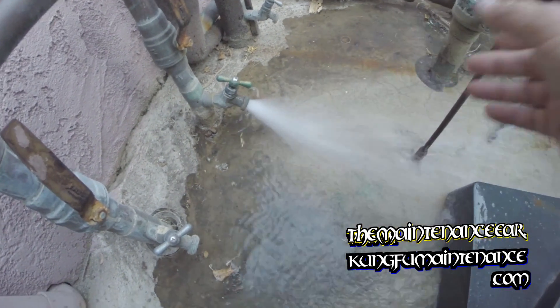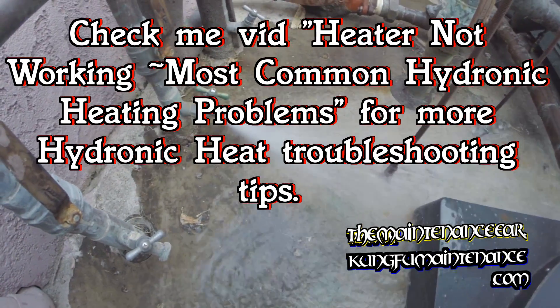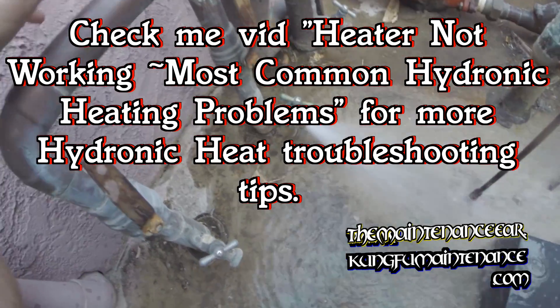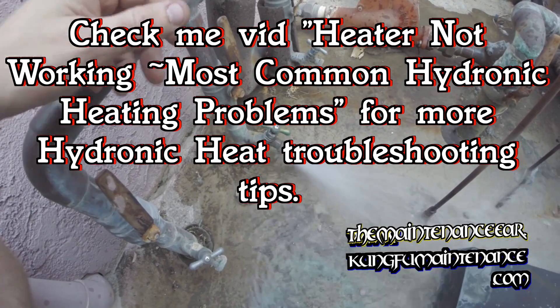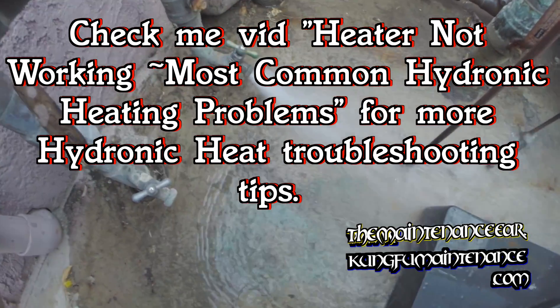For my system this doesn't happen too often, but for some systems this is just a regular maintenance item — purging the lines. Often it's needed at the air handler; you'd run a hose up to a bucket or a tub and drain the hydronic line to get that air bubble worked out and get things done again.